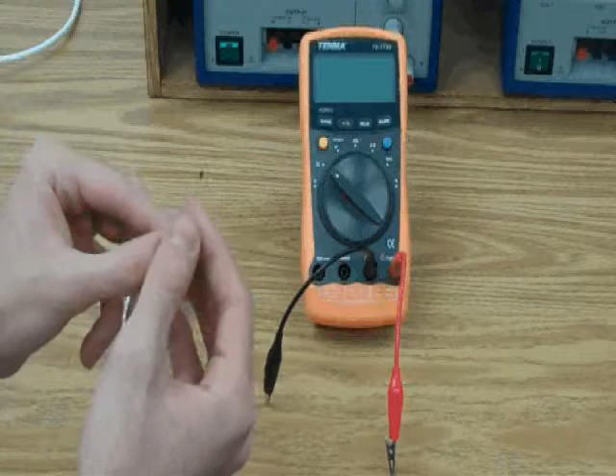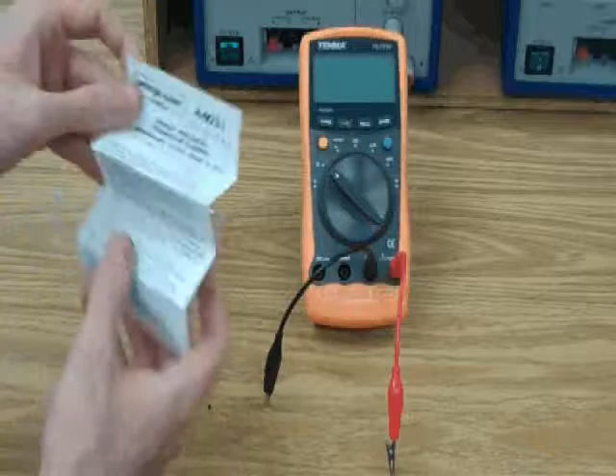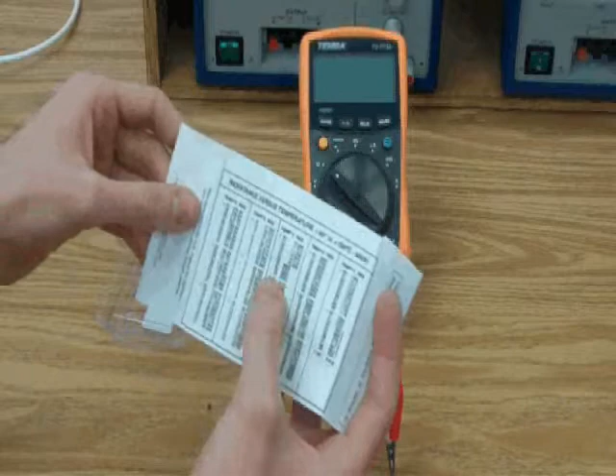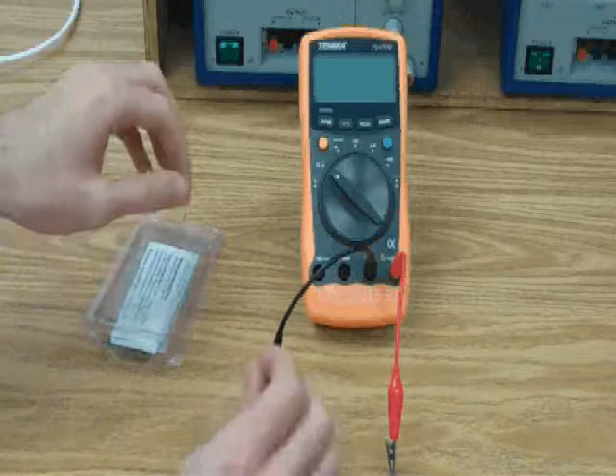This will change resistance as temperature changes. The other thing in our container is this piece of paper, and if we flip it over, we see it has a resistance versus temperature table, all the calibration we need. So we can look up, if we measure resistance, what temperature that corresponds to for this specific instrument. Now let's take a look at operating our thermistor.